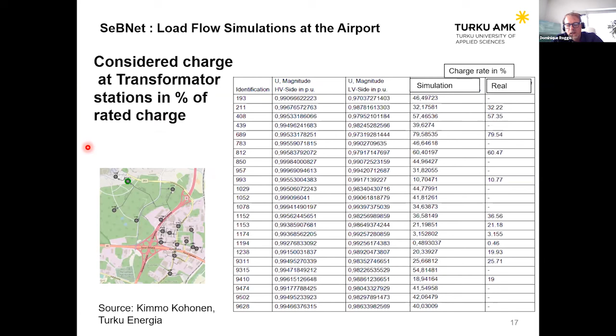The grid is very well dimensioned. So in per unit we got extremely low voltage drops, on the order of a few volts, which was about what we expected in the simulation. So the voltage drop in the simulation corresponds very well to the measurements—below 1%, as said before.